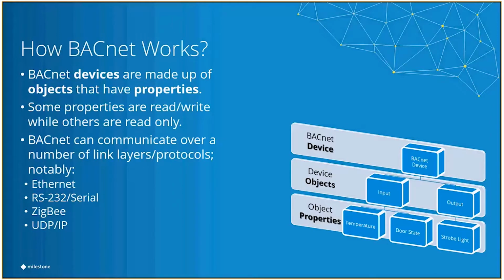One very important thing I found out about BACnet is it's not a programming language. It's not a scripting language. So you're not telling another system to do something. All you're doing is sharing data between systems. What happens with that data really depends on how that system's programmed. So in the case of XProtect, our rule engine, our alarm engine, is going to be what drives the data from BACnet.